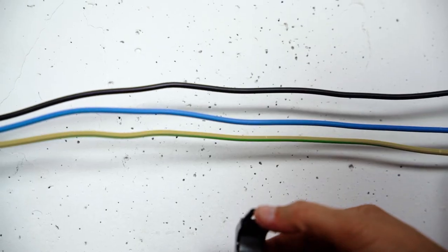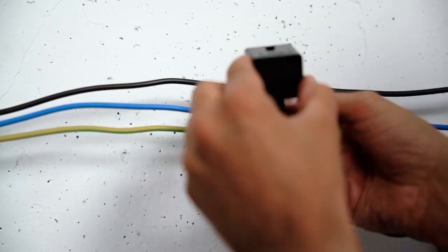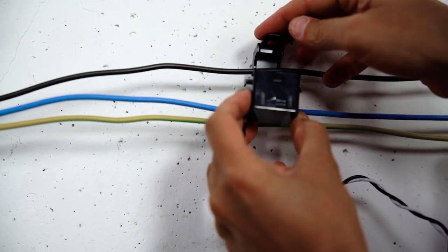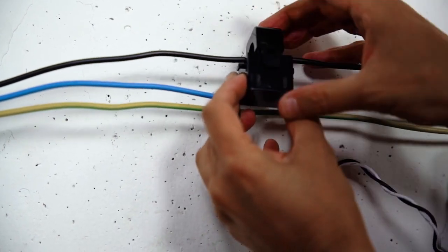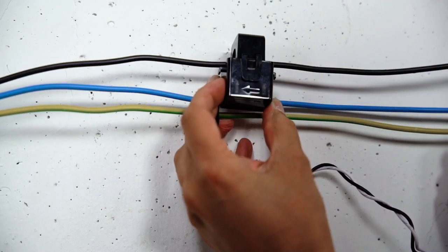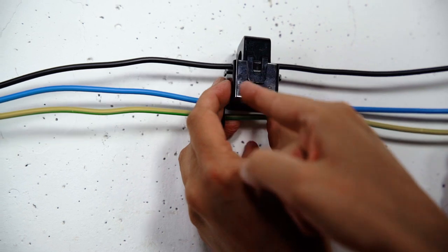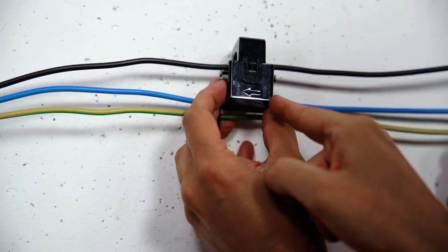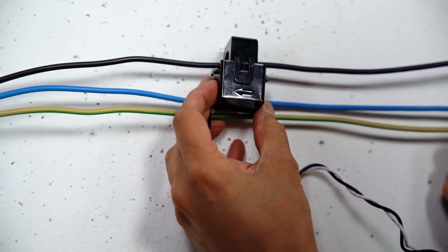The CT of the meter must be clipped around the house line cable. It is essential that the CT is connected at the house grid connection point so that the whole house is behind the meter including the backup load. Pay attention to the orientation with clipping the CT. The little arrow has to indicate the direction from grid to house load.